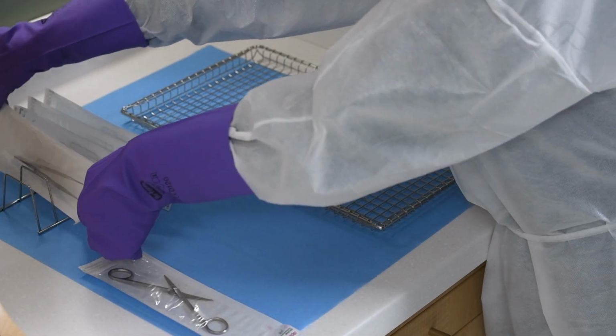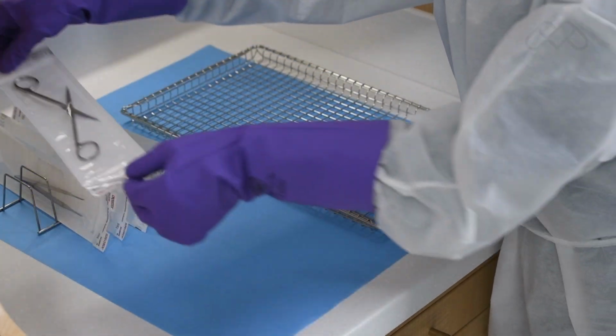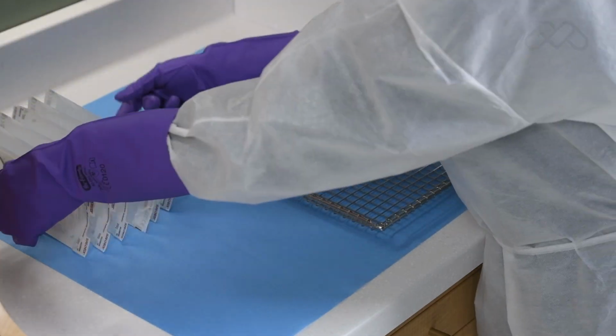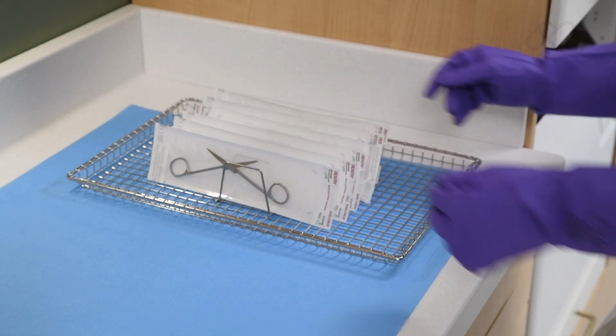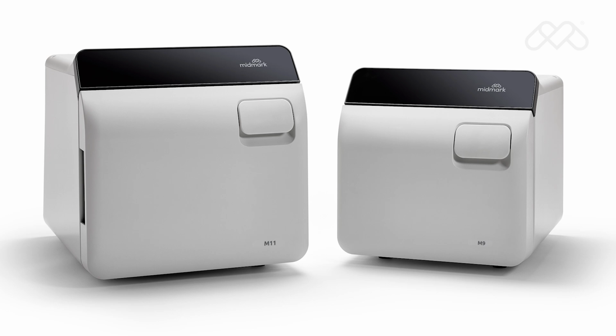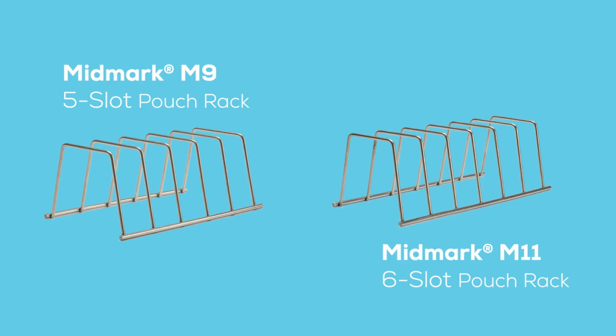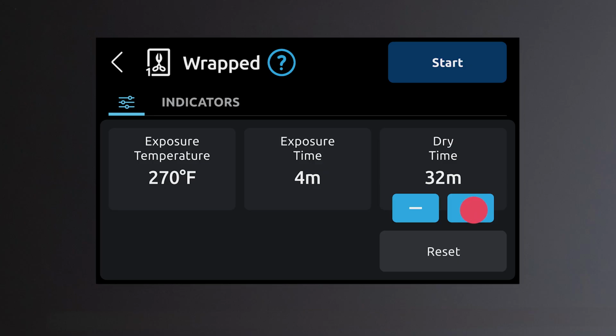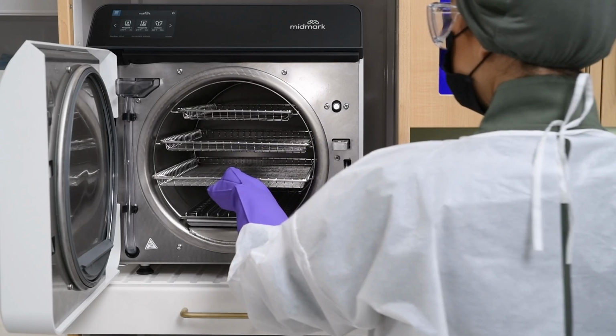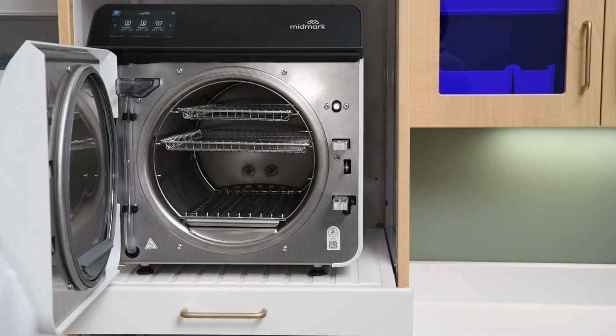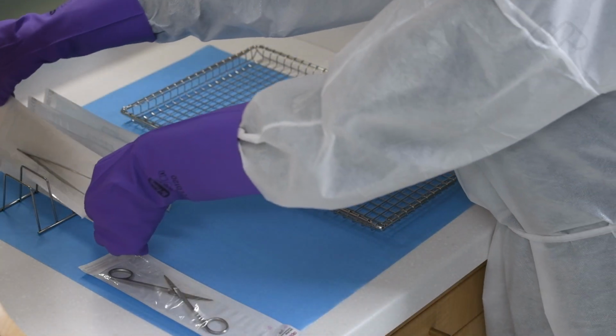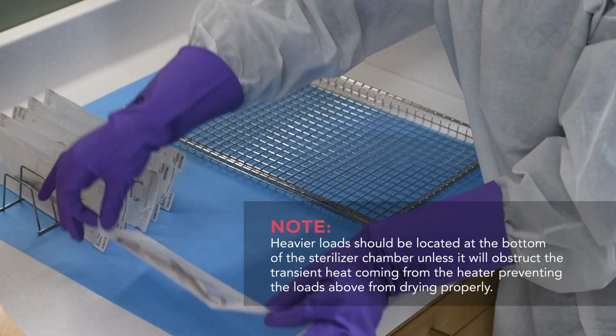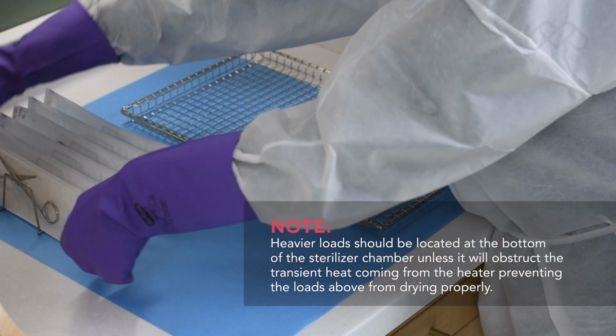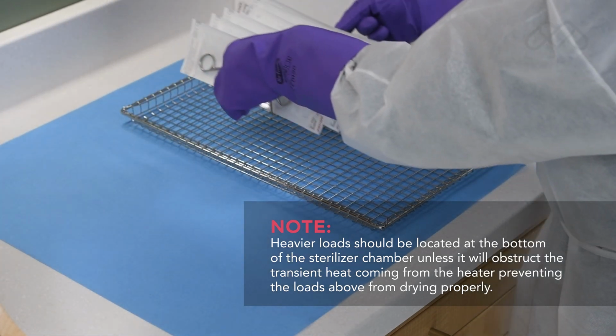For proper steam circulation and drying, the preferred orientation of pouches is resting on their edge, best accomplished using the Midmark pouch rack, supplied with the M9 and M11 steam sterilizers. If additional pouch racks are needed, order using the appropriate kit part number. If more than 2 pouch racks are used in a single load, additional dry time may be required. The use of a pouch rack requires the removal of some of the sterilizer trays. When using a pouch rack, load a single pouch per rack slot. Orient pouches in the rack so the plastic side of one pouch faces the paper side of the adjacent pouch.